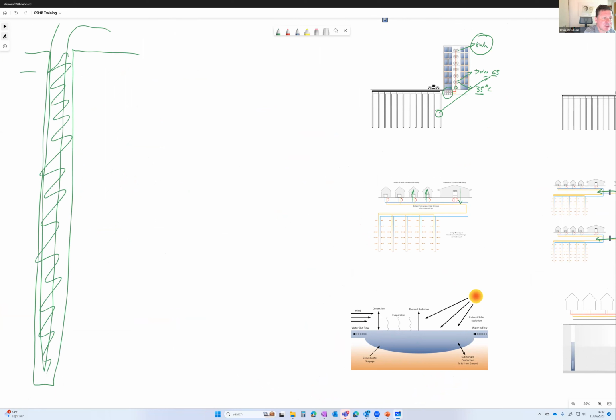The boreholes here are quite narrow diameter, only about 150 millimeters, can be even less, can be more. They typically go from 100 to 300 meters deep - that's the kind of depths we tend to see. So that's vertical boreholes, ubiquitous really for commercial ground source.